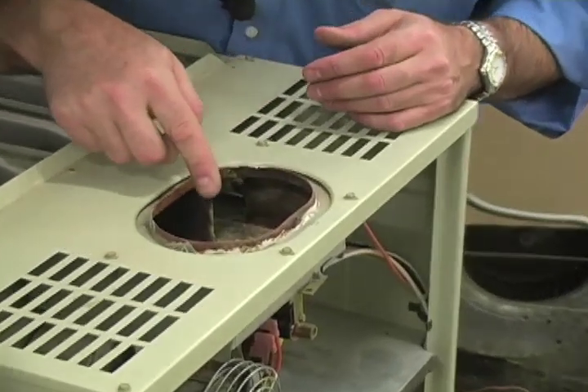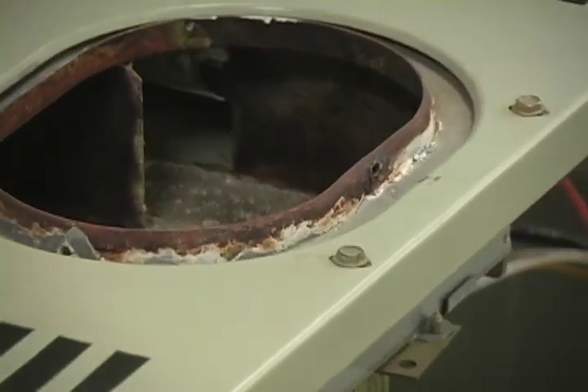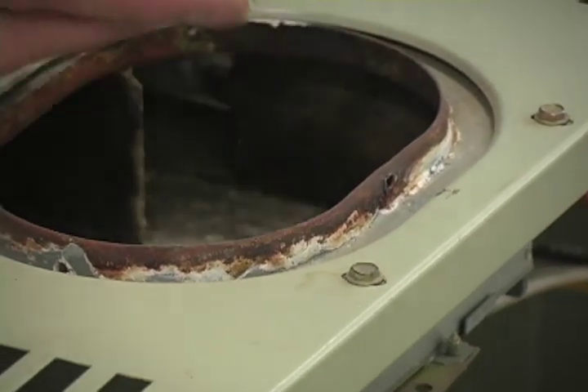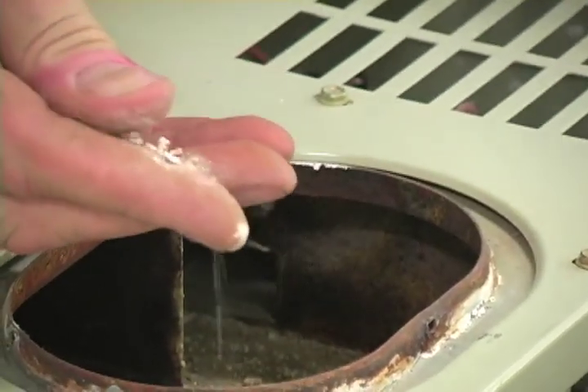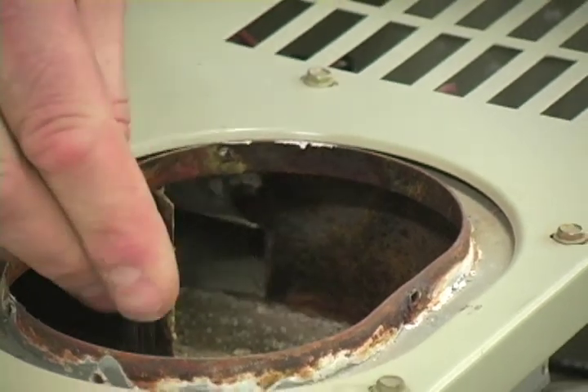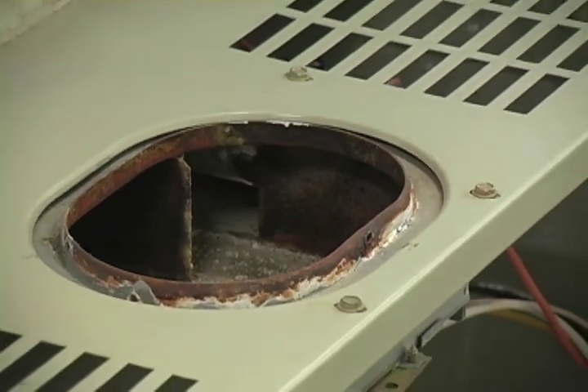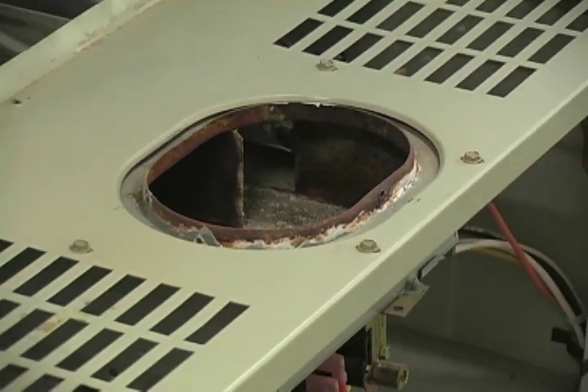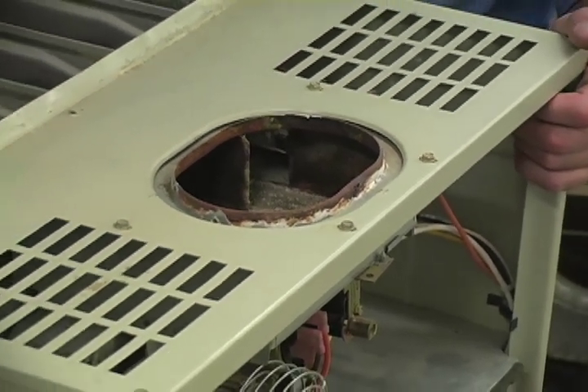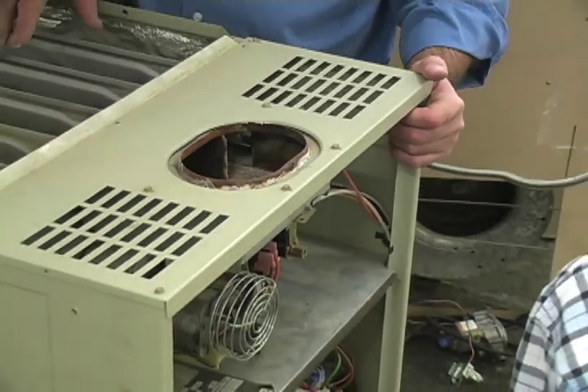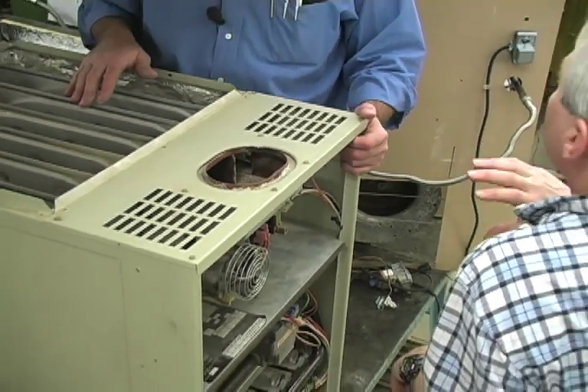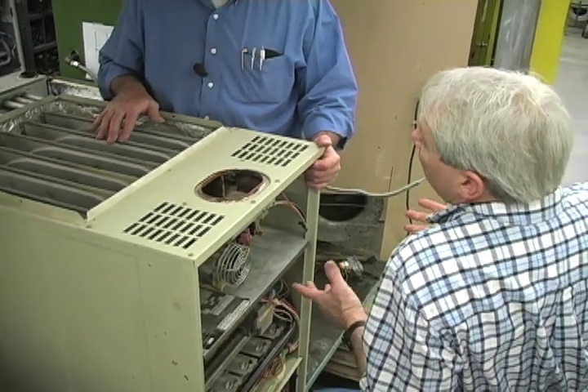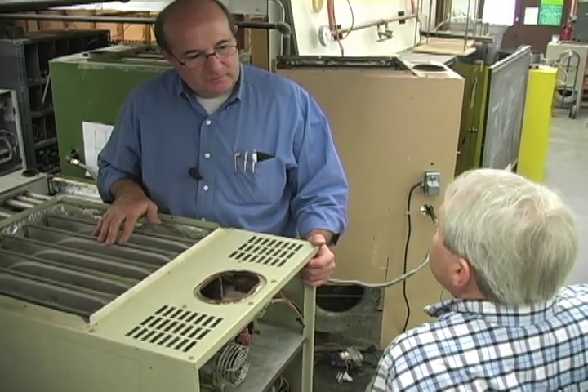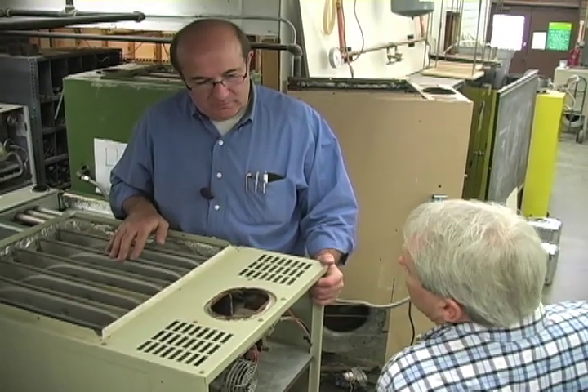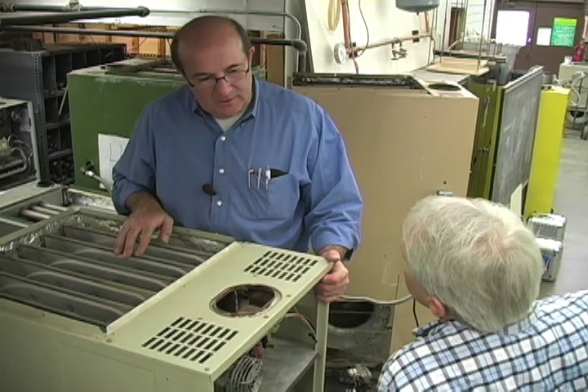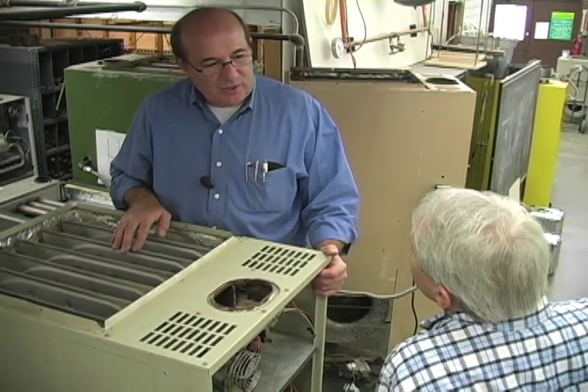And also, you can see inside here quite a bit of corrosion. Looks like there's some more zinc oxide, some mineral salts, and lots of rust flakes and powders. We often see improperly configured exhaust vents that either have inadequate slope or are too long, or for one reason or another, the exhaust gases are cooling down and causing excess condensation that runs down and causes problems like this. Yeah, it's a typical problem.